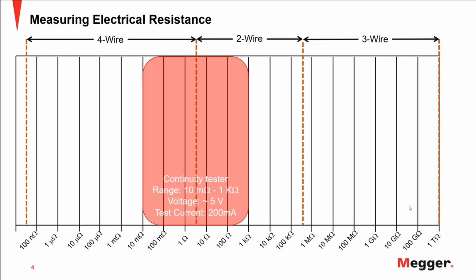Next, we have much lower resistance measurements from 10 milliohms to 1 kilo ohm. And this is typically the continuity tester, which is probably a functionality in many or several digital multimeters. And you could have a little bit better accuracy or lower measurements there, on the lower side of the range, but still it's not going to be that accurate because the voltage and the current that they can use might be limited.